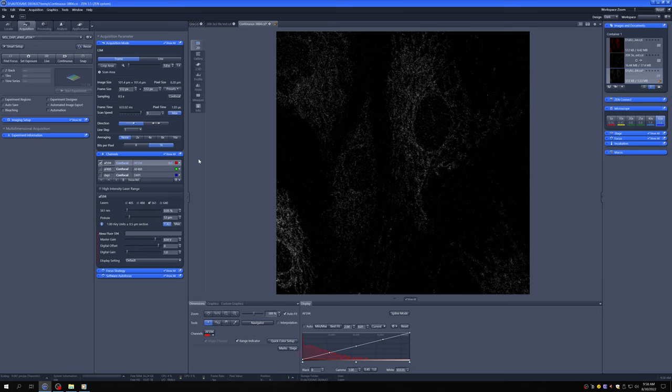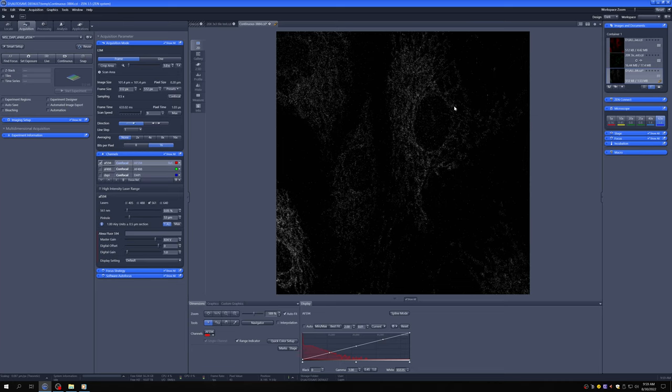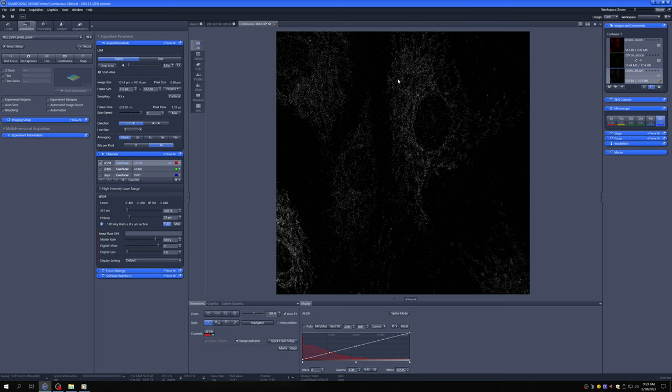There is another parameter that you can adjust that also can affect the quality, which is the speed. Remember this is a laser scanning confocal. The microscope points the laser into the top left-hand corner of the sample and then moves in a raster pattern. As it does that, it's moving at a certain speed, which is controlled by this slider. So if you lower the speed, you expect the frame time to take longer, you expect more bleaching because the laser is on the sample for more time, but you also expect higher quality because you have the opportunity to get more light, more fluorescence light from each location.